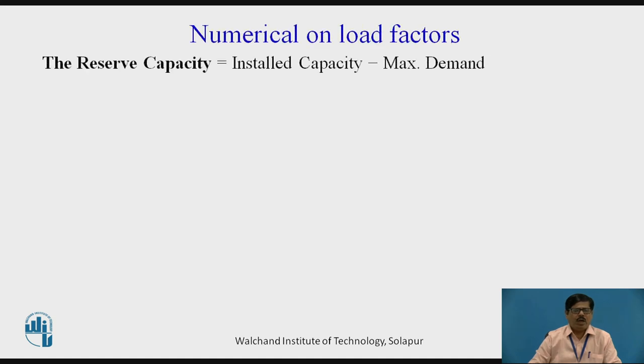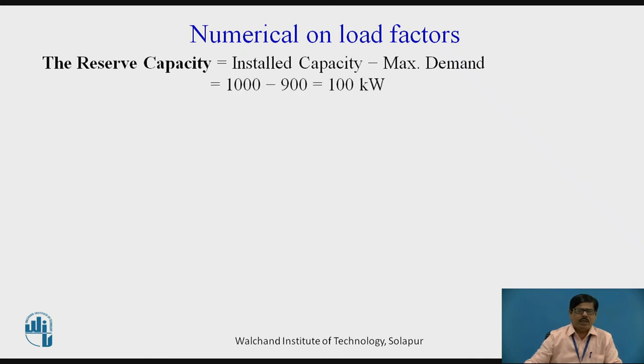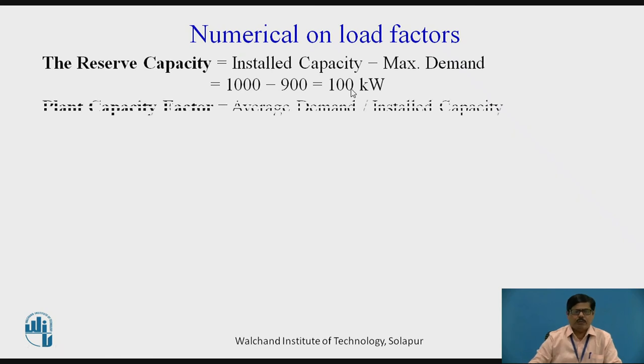Now let us see how to find out the reserve capacity. The reserve capacity equals installed capacity minus maximum demand. The installed capacity of the power plant was 1000 KW, whereas the maximum demand was 900 KW. So the reserve capacity is obtained as 100 KW.